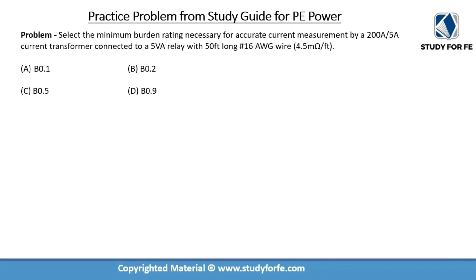Let us look at a practice problem from the study guide for PE Power. We are asked to select the minimum burden rating necessary for accurate current measurement by a 200-to-5-amp current transformer connected to a 5 VA relay with 50-foot-long number 16 AWG wire having an impedance of 4.5 milli-ohms per foot. We need to systematically process the information and use our burden formula to calculate the minimum burden rating.